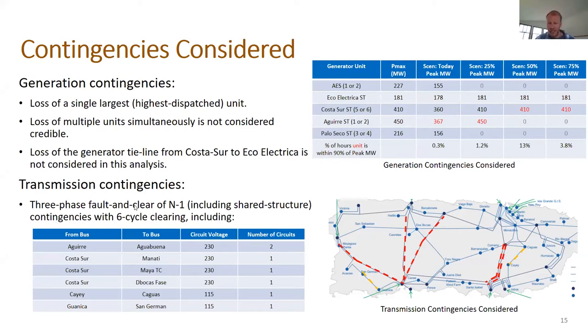The transmission lines considered are also shown graphically on the map, where we're looking at the major paths, the red lines being the 230 kV or the highest voltage level on the island, including a double circuit contingency, as well as a couple 115 kV contingencies shown in yellow. We also presented and spoke with the PREPA engineering team, who provided some feedback and asked to add the 115 kV contingencies, and agreed that those are some of the most critical transmission contingencies for dynamic stability.